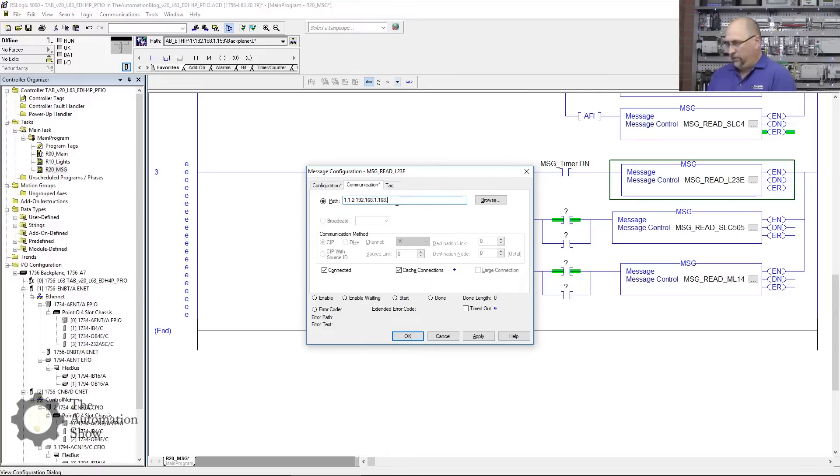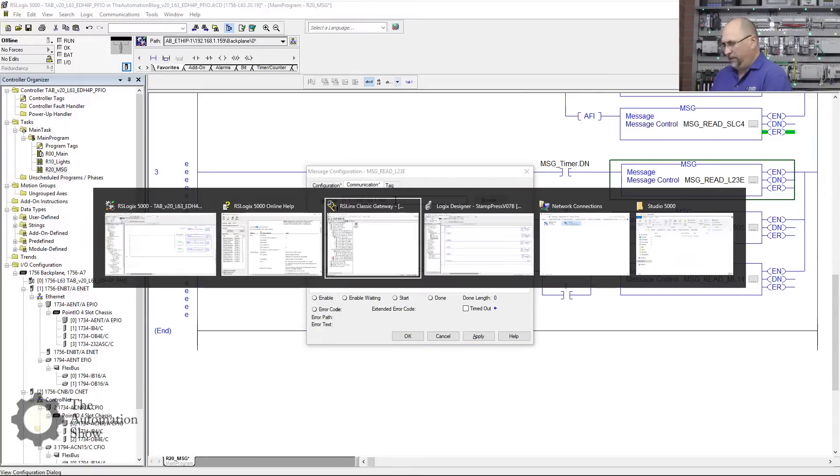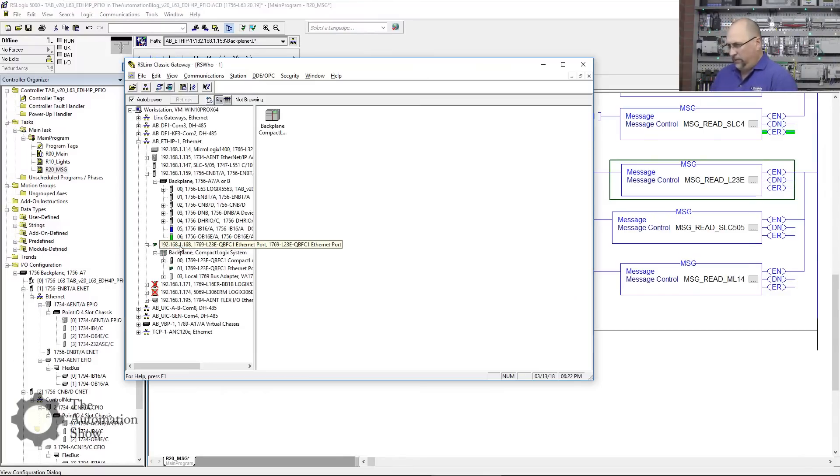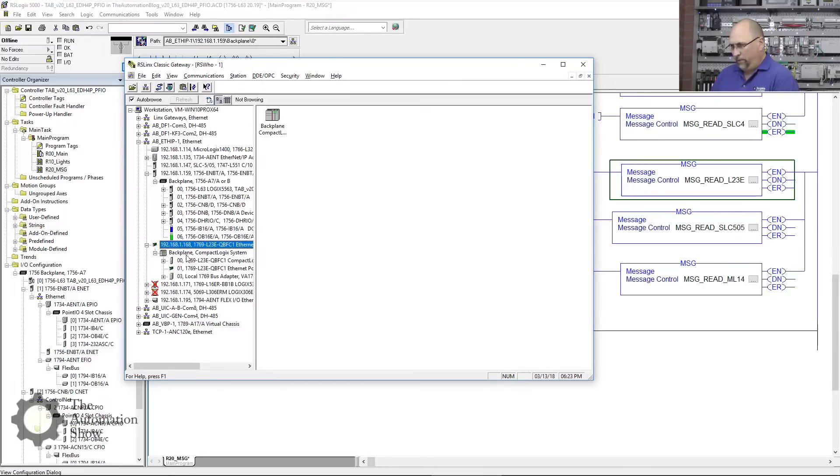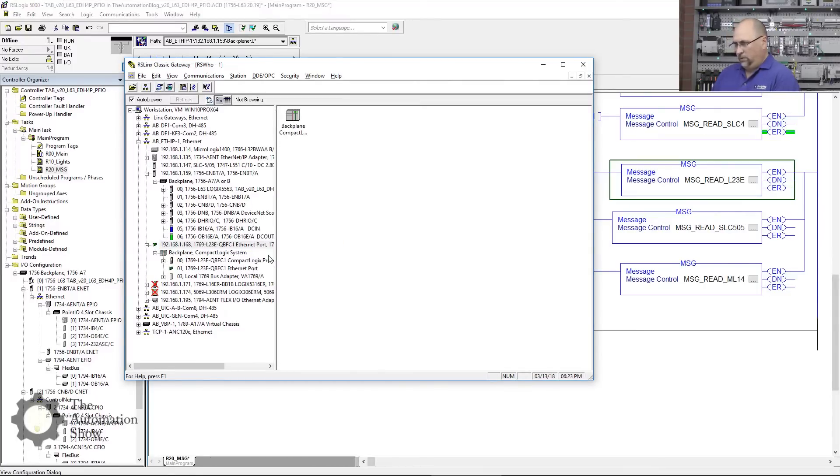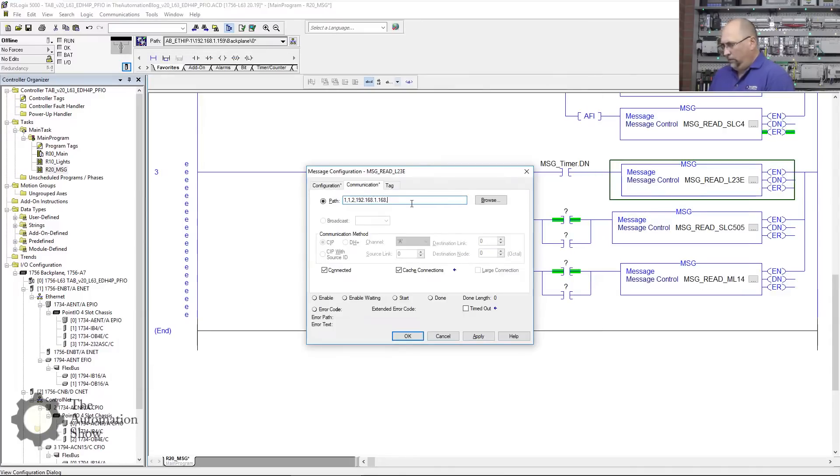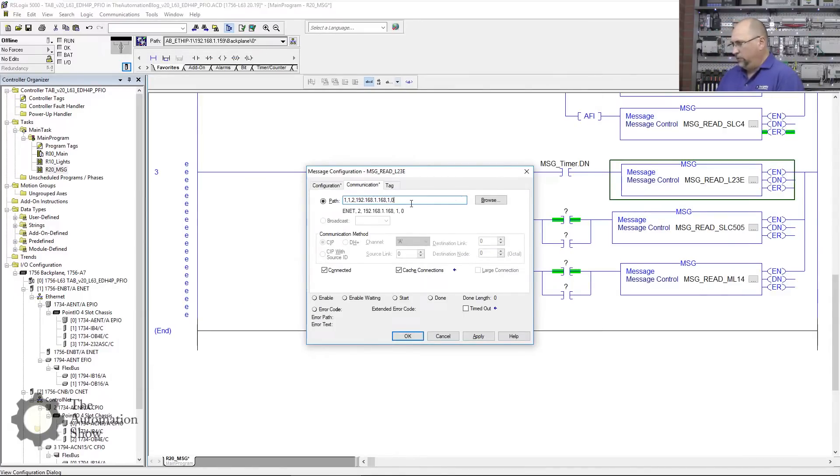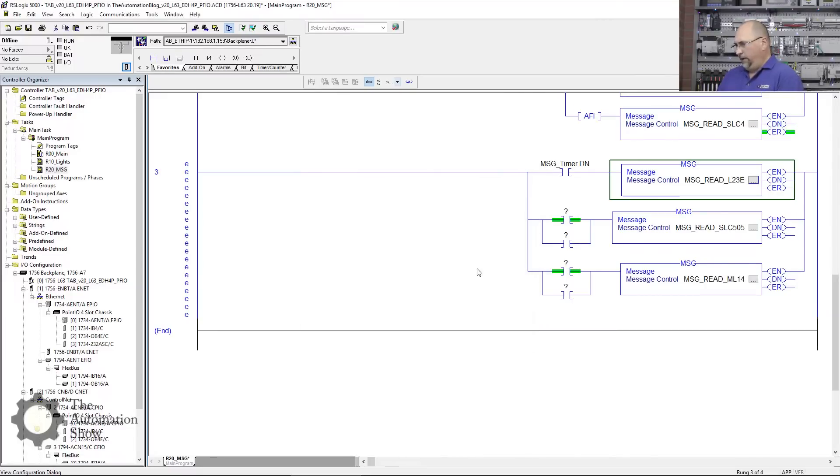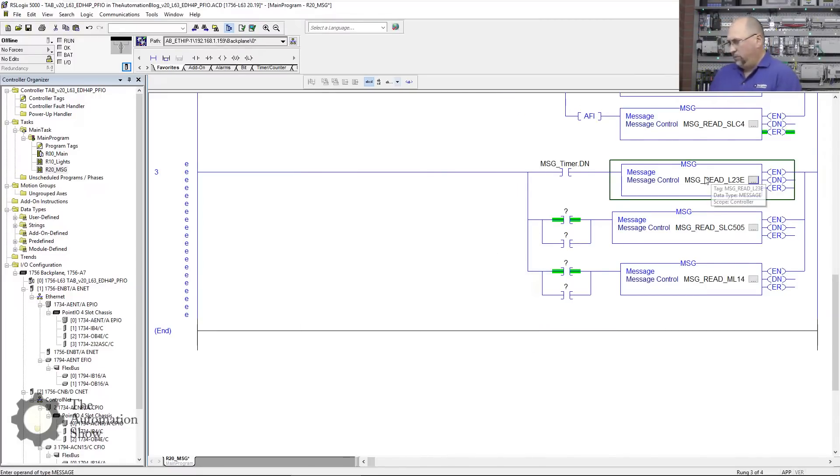Now if you look at this, after I put in that 168, I got some more information I need to put there. The next thing I have to do is go to the backplane again, because you can see it looks like a little Ethernet card, then there's a backplane, and then there's a slot zero for the controller. So we need to do 1 for the backplane and then 0 for the controller. We'll apply that and click OK.